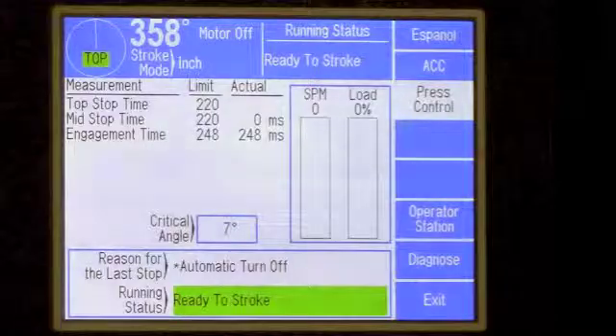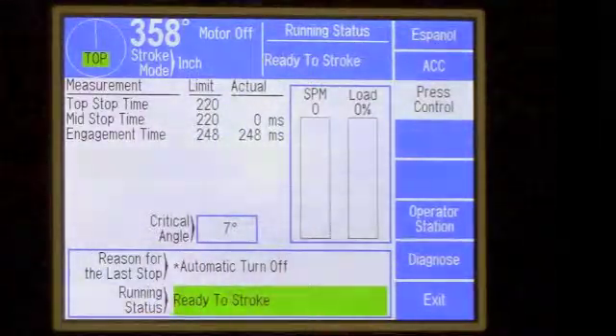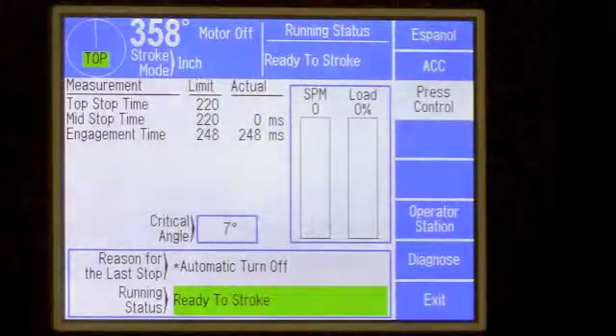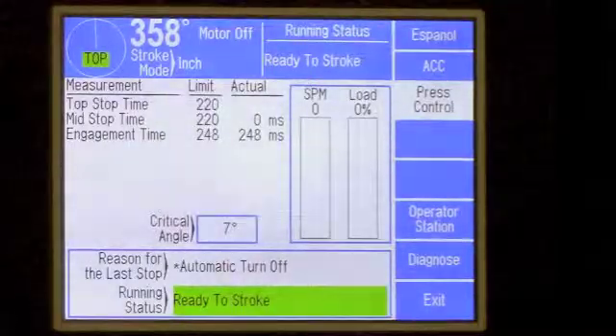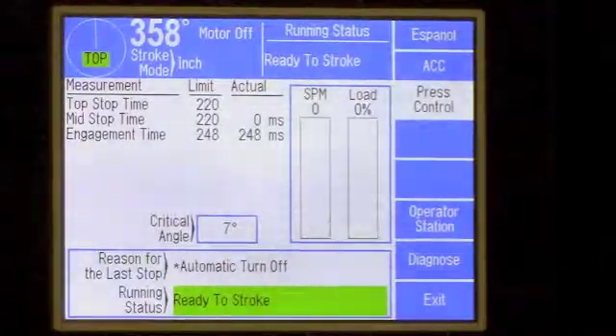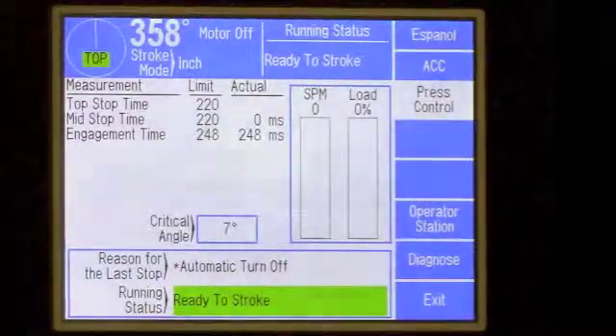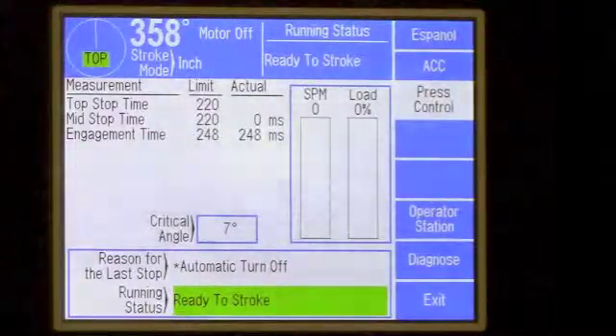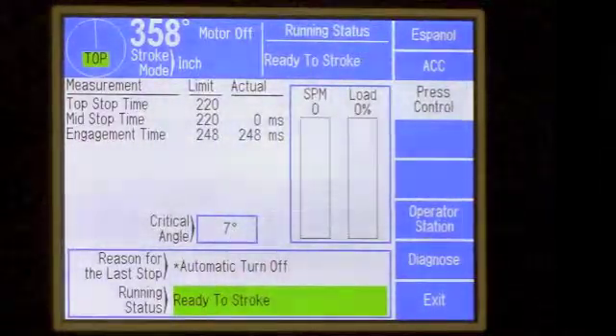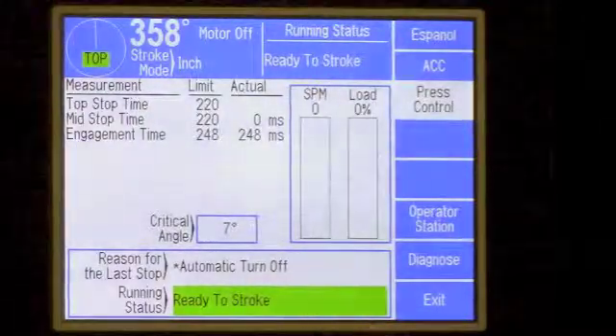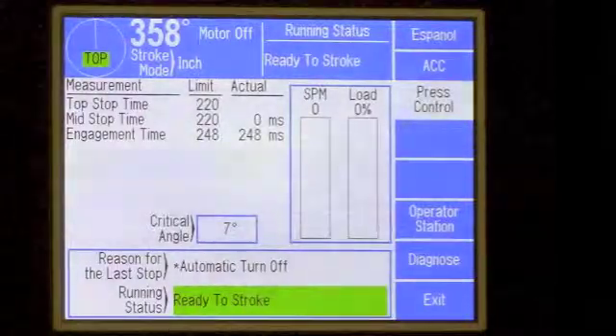The main two areas we want to focus on are the reason for last stop and current running status. This information tells you the status of the press control. When the running status is green, it will say 'ready to stroke,' meaning the press is ready to make parts with no problems registering. If you do have a fault, this will go yellow or red depending on what fault you encounter, and it will also give a brief description of what the fault is.